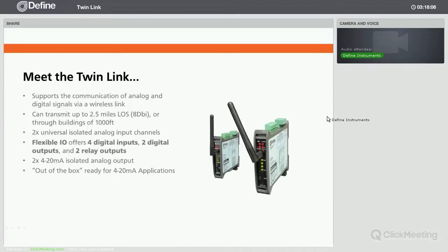The most common question we get asked about the TwinLink is, what's the transmit range? The transmit range between your TwinLink input and output unit is 0.9 of a mile, line of sight. Now you can extend this to 2.5 miles with the larger 8 dBi antenna. Within buildings, it can transmit through walls up to 1,000 feet. It has two universal isolated analog inputs that can measure 4 to 20 milliamp, temperature, resistance, potentiometer, and frequency. It will also transmit up to 4 digital input signals. This means that 4 digital signals on the transmitting unit will be sent to 4 digital outputs on the receiving unit, and vice versa. This is ideal for transmitting digital signals such as pressure switches and alarms.